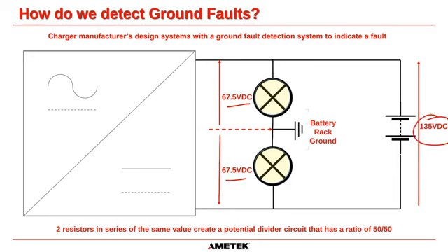Okay, so yes, the total voltage between positive and negative is 135 volts, but if you divide that by 2, you get 67.5, and that's what you should see between this point here and this point here, and from this point here to this point here. And because we tie this center point down to ground, you now have 67.5 volts between negative and ground, and 67.5 volts between positive and ground. So we have deliberately created a reference to ground. But because these are high resistance resistors, it doesn't allow much current to flow between positive and ground and negative to ground. So we can control the current, and therefore somebody is still not going to get an electric shock if they touch the battery terminal, because there's only a minimal amount of current that can flow.